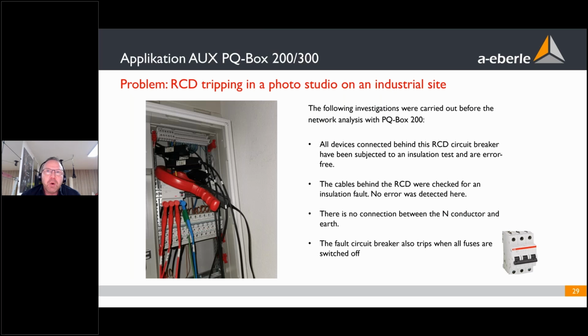Now, one power quality story with supraharmonics, where I used the fifth current input. There was a small photo studio, a designer studio, a small company in a big industrial area. In this office there was an RCD, and this RCD tripped many times a day, so the people couldn't work. The electrician of the company wanted to find out what the problem was with the RCD.